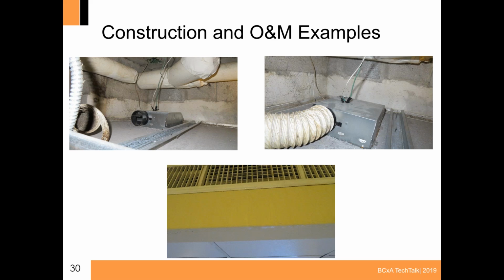These are problems with existing buildings. On the left, this is how we found literally every single room in a hotel. These are exhaust fans in a tropical environment, so if you're not dragging air through a hotel room there, you'll get big humidity and mold problems. Literally every single room had the exhaust ductwork disconnected, which caused the drippings you can see in the bottom picture.